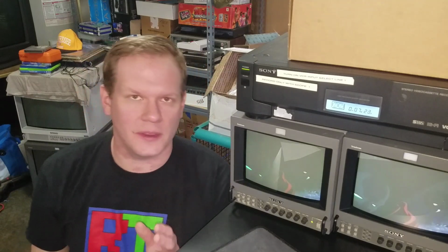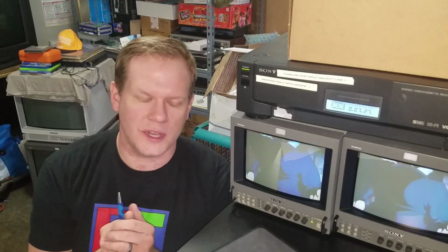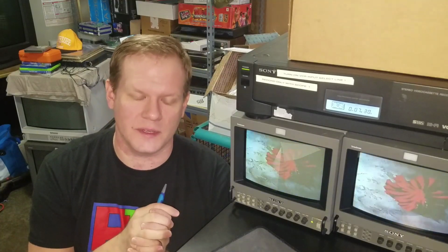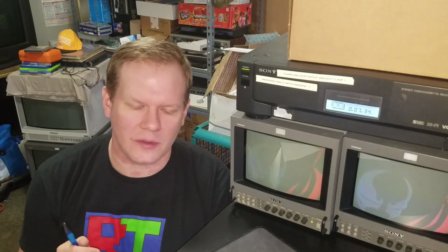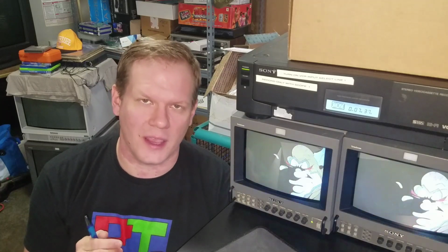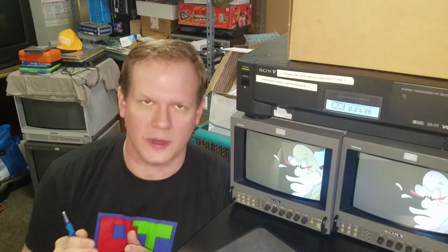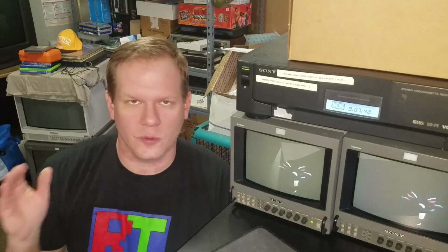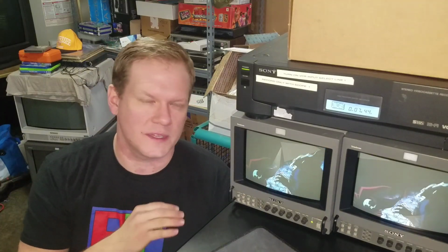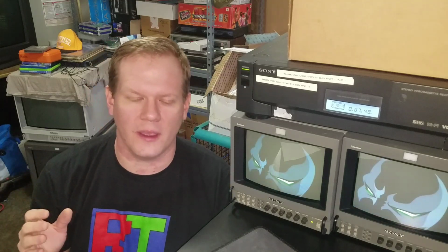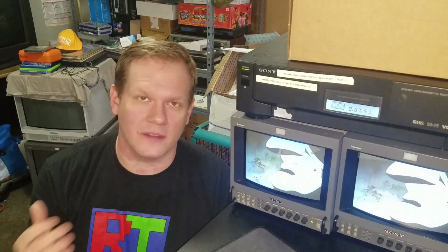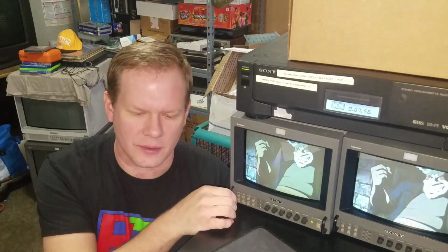Now storage is going to be a little different. It's got a higher tolerance than that because it's not in use. Storage temperatures are going to be between -10 degrees Celsius up to 40 degrees Celsius, which converts to 14 degrees Fahrenheit up to 104 degrees Fahrenheit. So you have an even larger window there. If you're storing your PVM in a storage unit or a non-temperature-controlled area, be aware that it's safe for it to get down even below freezing into the teens before anything can happen to it.